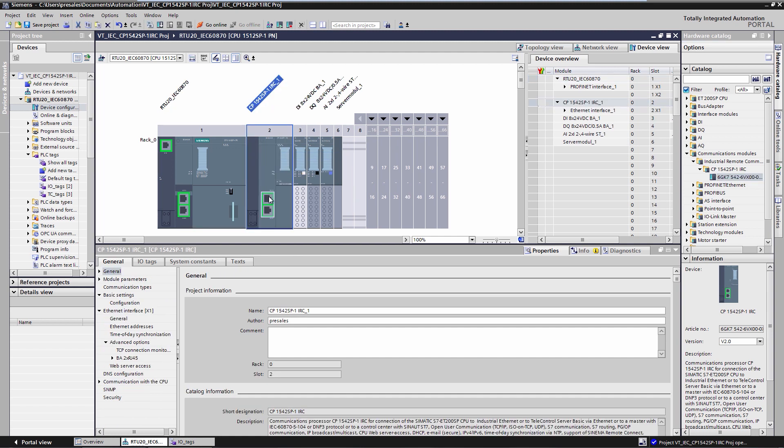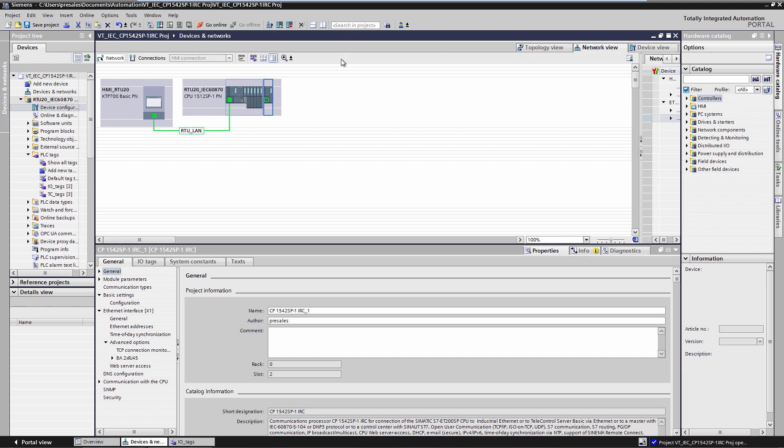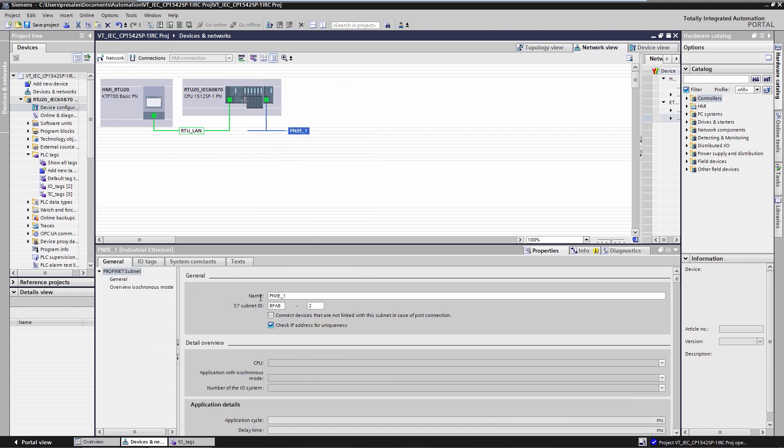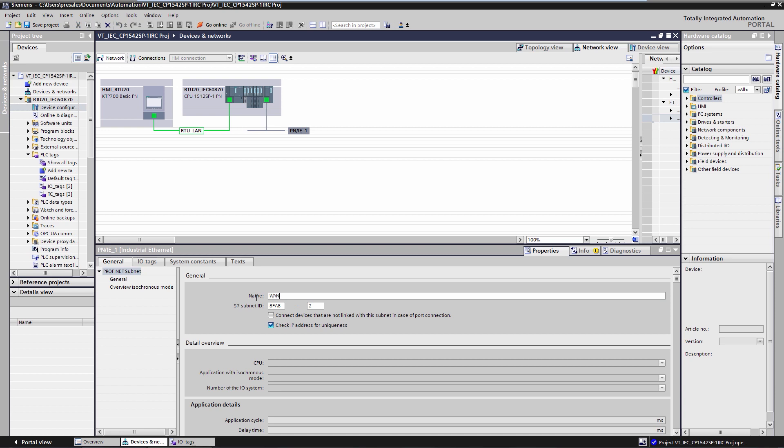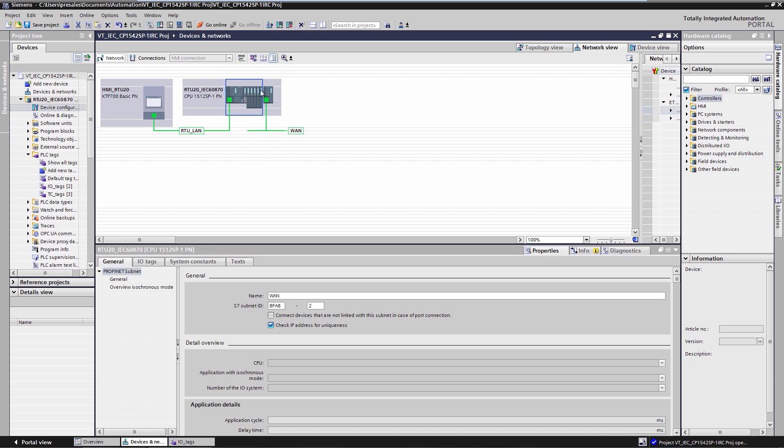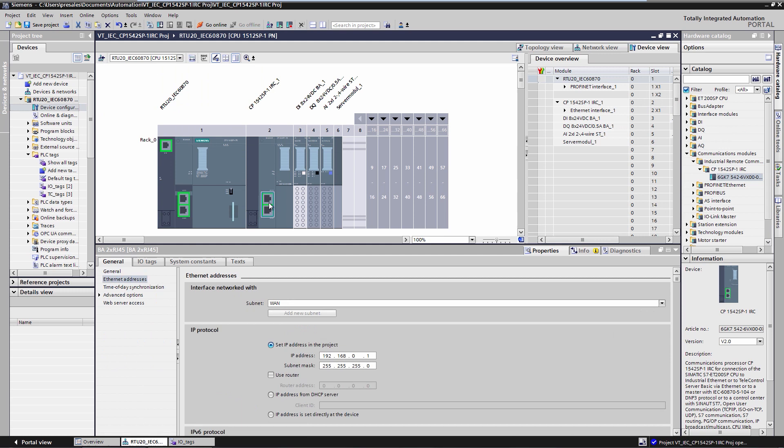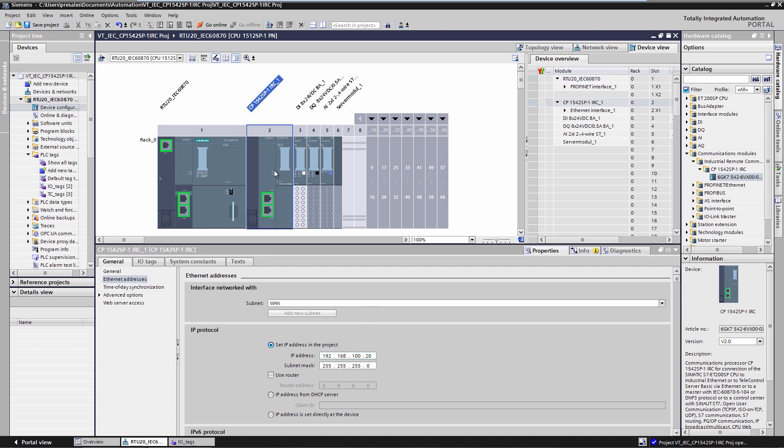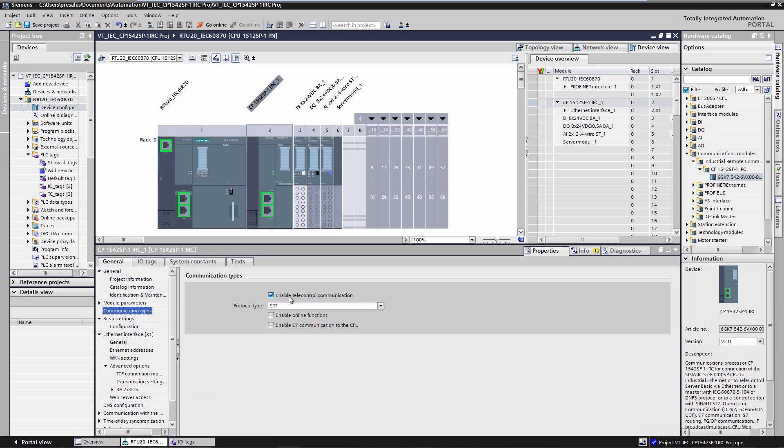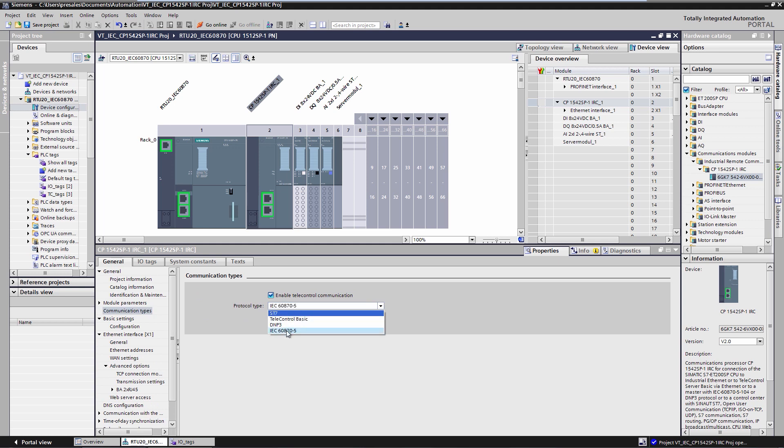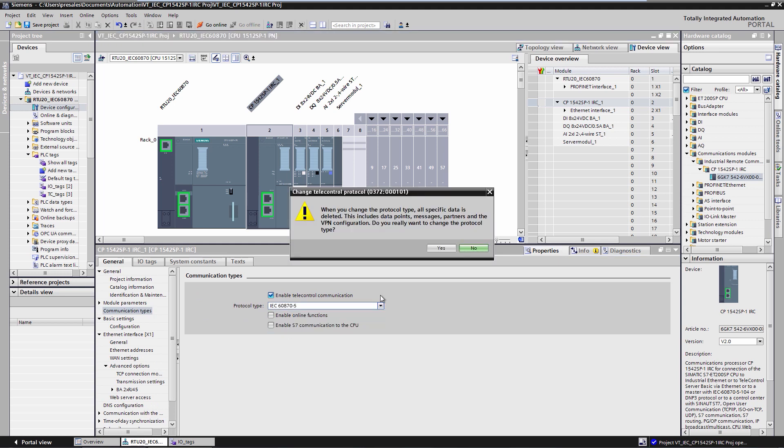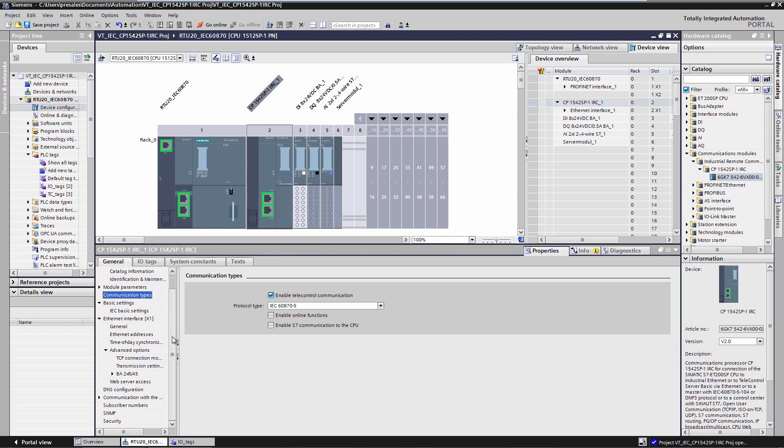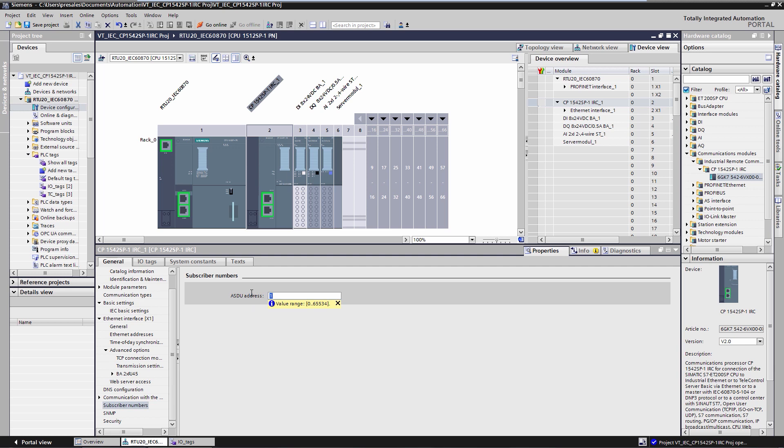Then I connect the CP with its Ethernet interface to a WAN for communication with the IEC master. Next, I configure the IP address with which the RTU communicates with the master. This IP address is 192.168.100.20. Now I select the communication protocol IEC 60870. Then I configure the IEC station address of my RTU, in case of IEC 60870, the so-called ASDU. The ASDU address is 20.